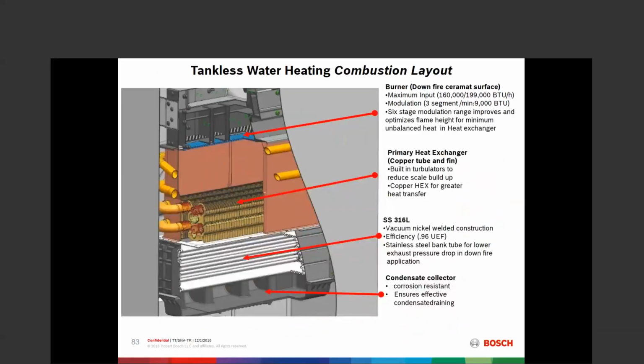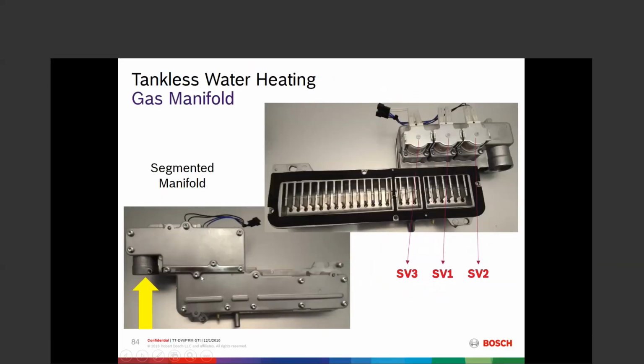An artist rendering and cutaway of what it looks like. We have our three segments here. Top three segments of the burner. 6 passes through the combustion chamber, 2 layers of 3 passes each, copper tubing with all copper fins, transferring the heat energy from the flue gas, and then our banked tubes of stainless steel tubes down here at the bottom, allowing for extracting all that latent heat of vaporization. Manifold itself segmented, so we have 3 valves that control each of the 3 segments. So segment 1 is valve 1, segment 2 is valve 2, and segment 3 is valve 3.